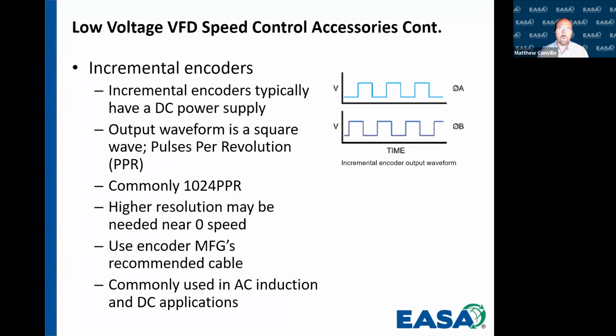So let's dig a little bit more into incremental encoders and resolvers. So incremental encoders typically have a DC power supply. And this power supply is usually somewhere between 5 to 15 to 24 volts DC. And then the output waveform that the incremental encoder produces is a square wave. And those signals are usually called A and A naught, B and B naught, and a Z marker. And the Z marker will tell you a revolution. Now these square waves come in pulses, as you see here.